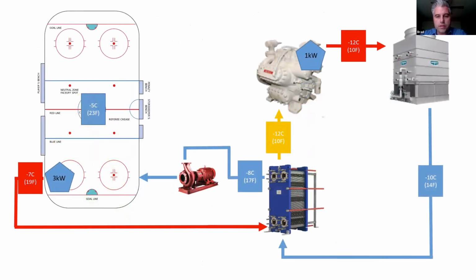As you can see here, typical arena refrigeration systems do not have heat recovery and end up wasting all of that free heat, sending it out and dumping it out the condenser, which is located at the back of the building. So all of that free heat you're already paying for is leaving the building.